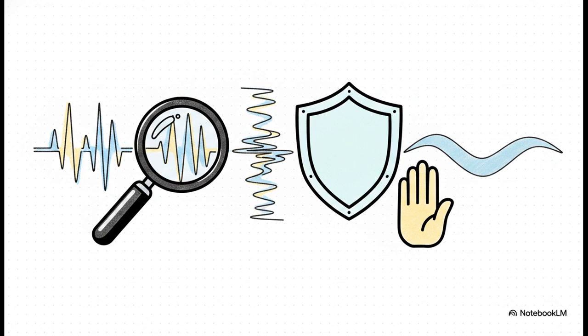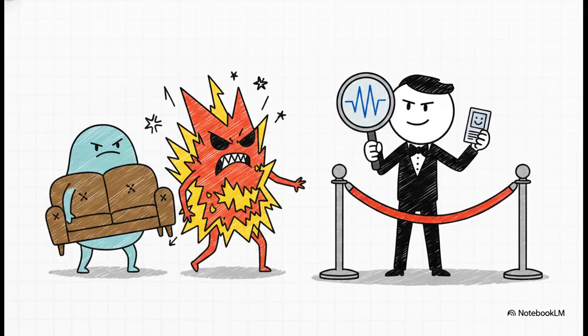The relay uses these specific signatures to essentially say, hold on and restrain or block the trip command. Think of the relay as a bouncer at a very exclusive club. A basic overcurrent relay just counts the sheer number of people rushing the door. But our differential relay actually checks their IDs. It checks the harmonic signature, so it can instantly tell the difference between a rowdy troublemaker trying to break things, which is a real fault, and someone who's just walking awkwardly because they're carrying a giant piece of furniture.